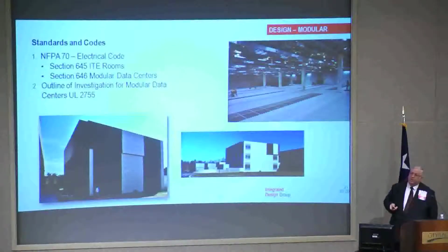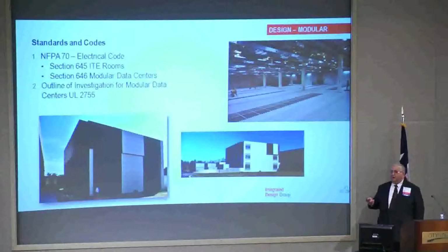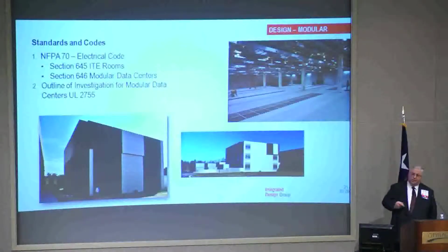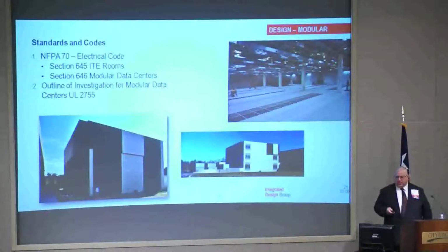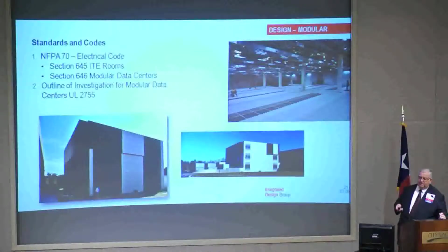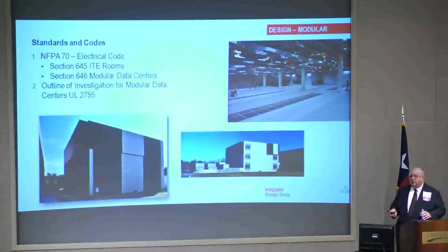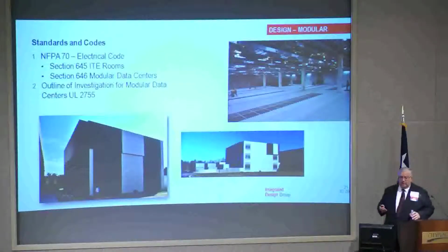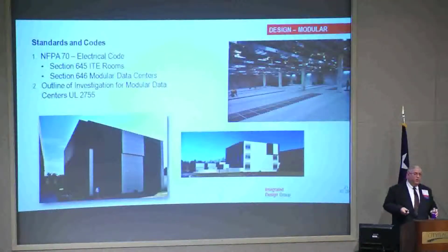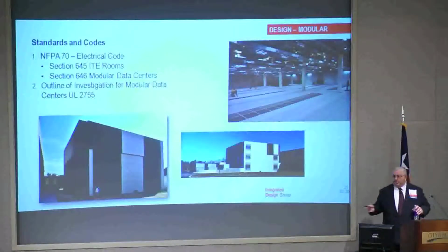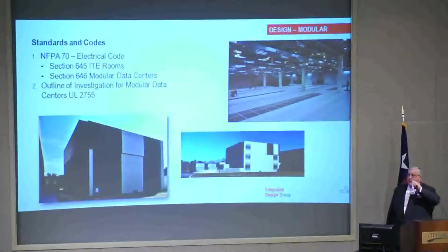UL has also come up with UL 2755, which they will use to certify a modular data center. It used to be a free-for-all as far as what a data center was and what it was built to. Now there are very specific code requirements, both in the National Electrical Code, which in most local jurisdictions is code, and since there's a UL requirement as well, many places require UL certified devices, so you'd have to get that certification too.